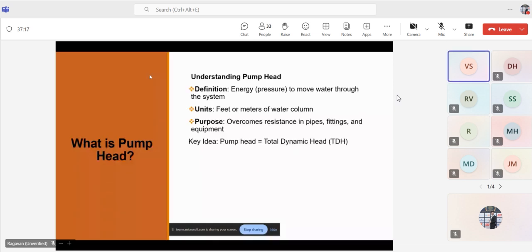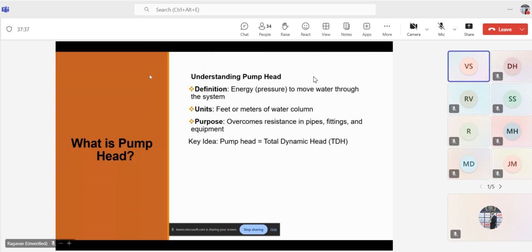Okay, so first one, what is a pump head? The pump head is often referred to as the dynamic head in the context of a chilled water system. It is the total energy that the pump must impart to the fluid to overcome all resistance and move it through the system. It is a measure of the pressure or energy required to deliver water from the pump to the farthest point in the system, accounting for the elevation, friction, and other losses.